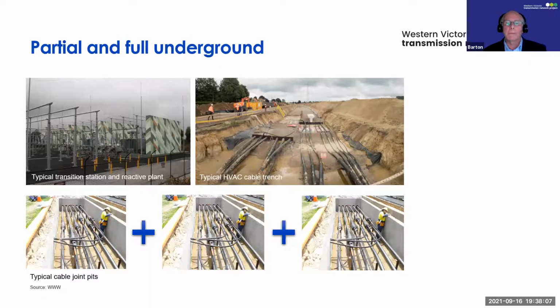There's another example of a high voltage AC cable trench - that's 400 kV, a bit less than the 500 kV proposed for this project. As mentioned, because we need to join up to 18 cables, you effectively end up with three cable pits side by side, as seen at the bottom of that slide.